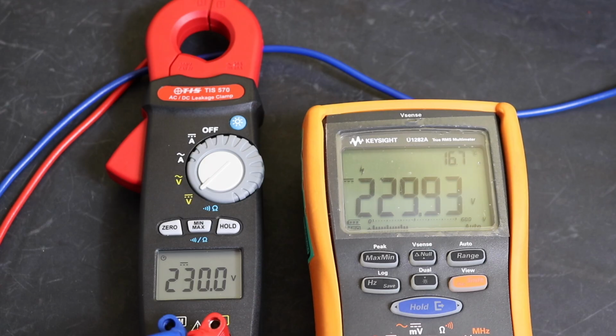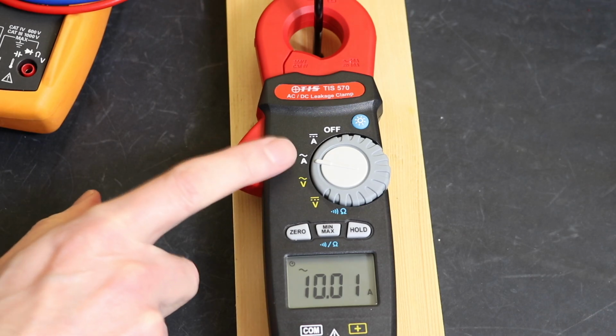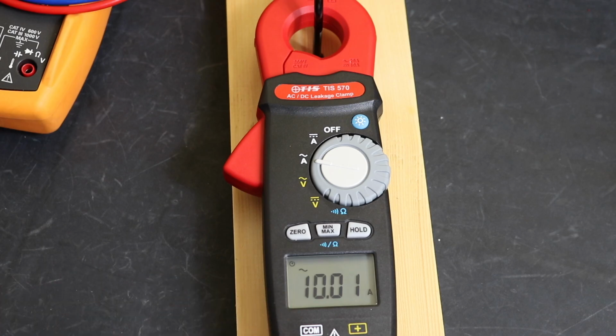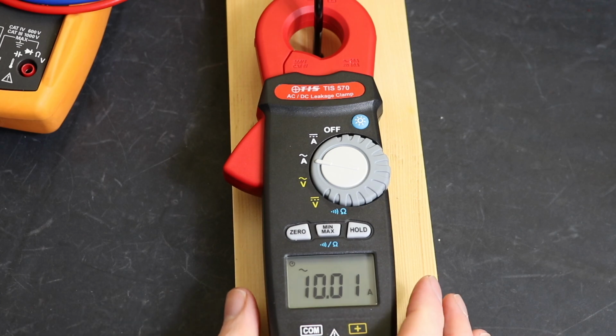So now I need to have a change around to test the current function on the clamp. So we are set up on AC amps here, injecting 10 amps, which is 50% of the full scale. Max we can read is 20 amps. We are 50 Hertz. And you can see we are 10.01, so pretty much smack on.